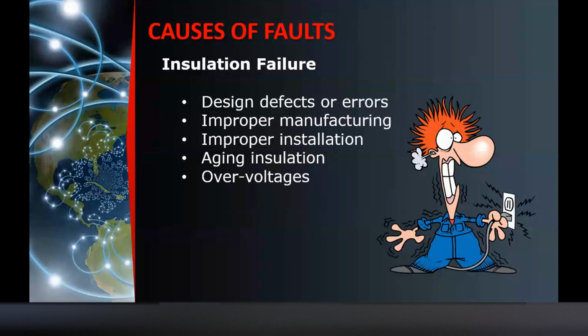Kung meron kang over voltages sa system, usually ang pwedeng maging cause niyan talaga is insulation failure. For example, nagkaroon ka ng single line to ground fault, meaning your one phase or one line is grounded. Nagkakaroon ka ng over voltages minsan doon sa surge arrestor mo. Pag bumabad ang fault, hindi nag-trip ang circuit breaker mo, definitely talagang sisirain niya yung insulation level mo, or yung tinatawag na BIL, basic insulation level. It is more on insulation coordination, so hindi na natin masyadong i-emphasize yun.